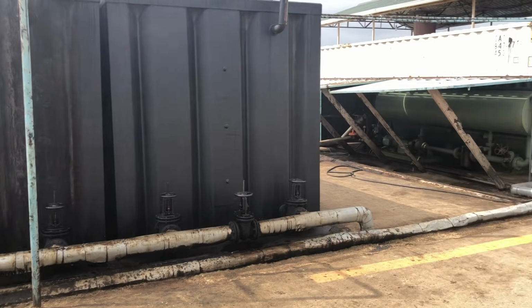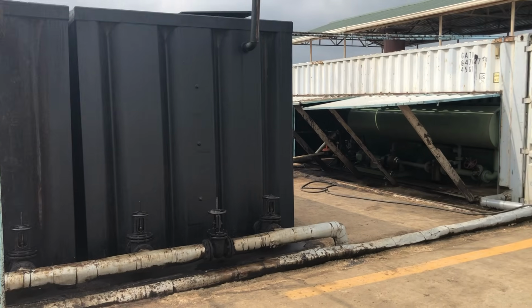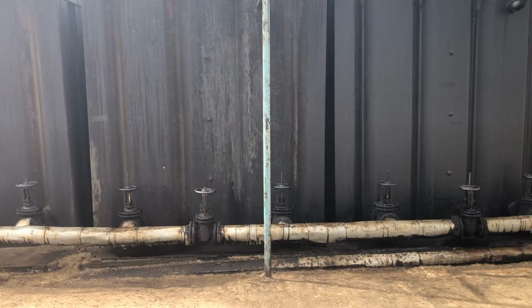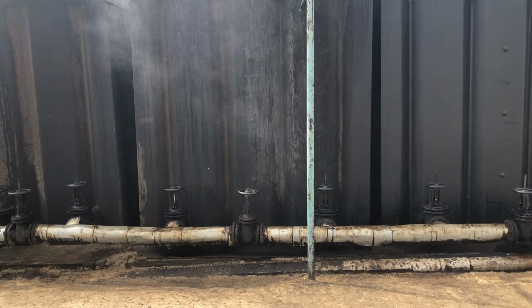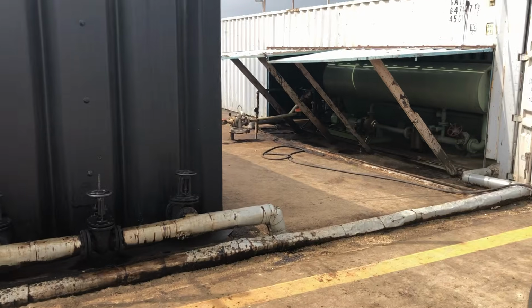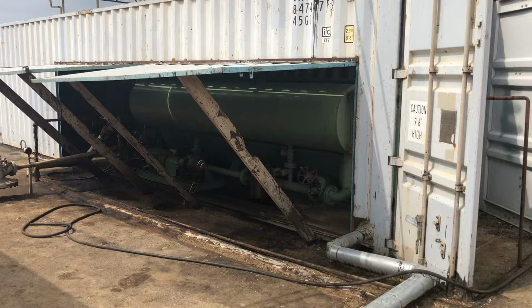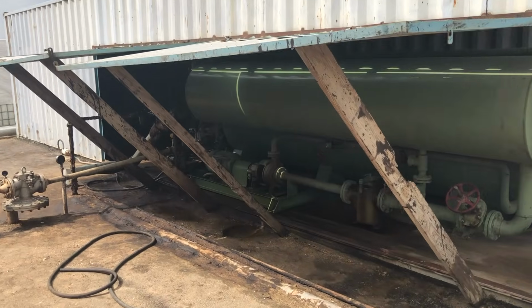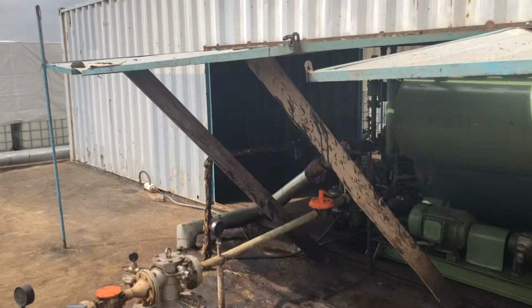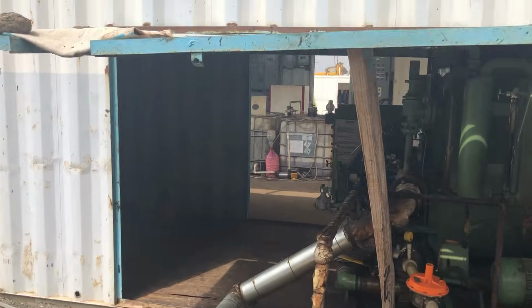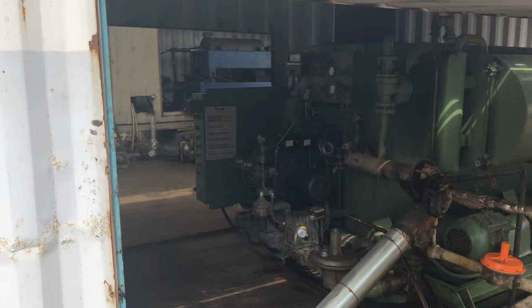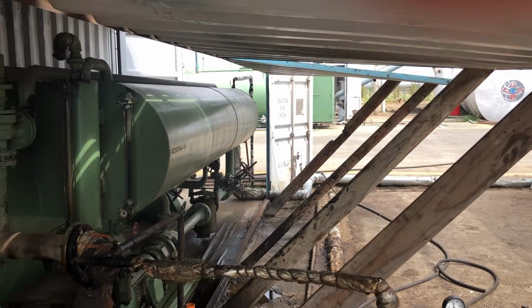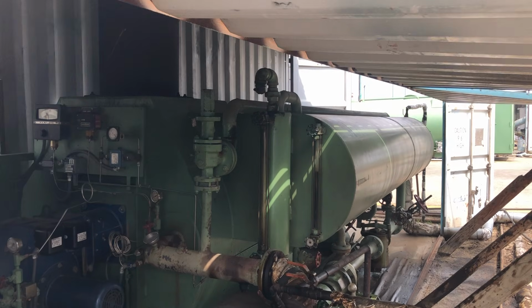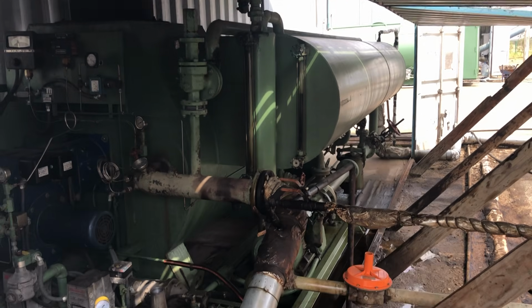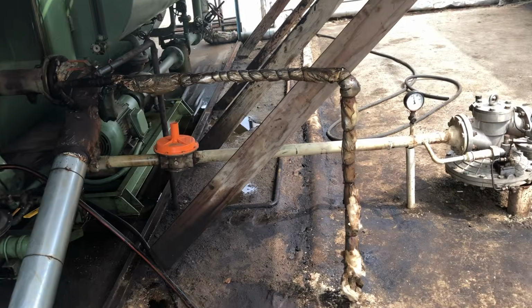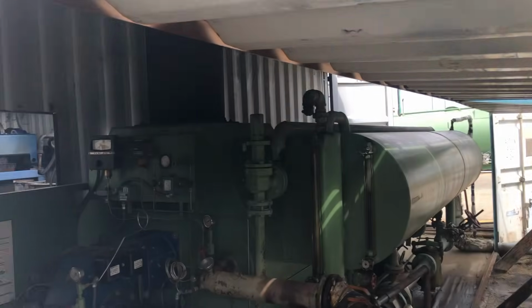These tanks are heated with thermal fluid from this thermal fluid heater. The oil flows through this manifold, and we can adjust the amount of fluid going to each tank, thereby controlling its temperature. The heat source is this 4.5 million BTU thermal fluid heater. This heats up the thermal oil coming back from the tanks. Goes through this burner coil system. Comes out here and flows back to the tanks.